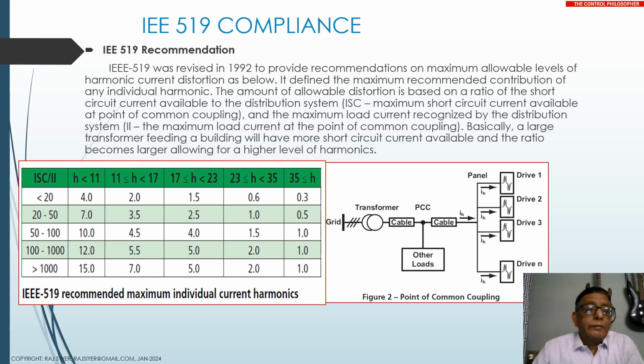And what does the second line mean? 20 to 50. When you say that the other loads at the point of common connection and the sum total of the VFD loads are between 20 and 50, that means you are operating at less than half the current of what was shown in the first line. That is why he is allowing a higher harmonic content. So finally it boils down to the fraction of the transformer capacity that you're using.